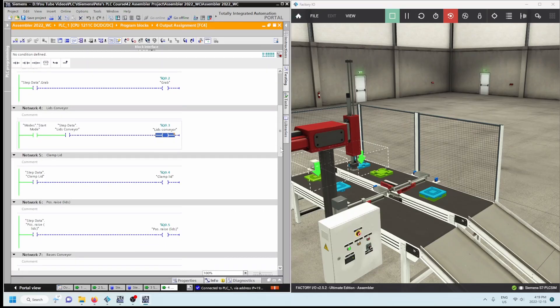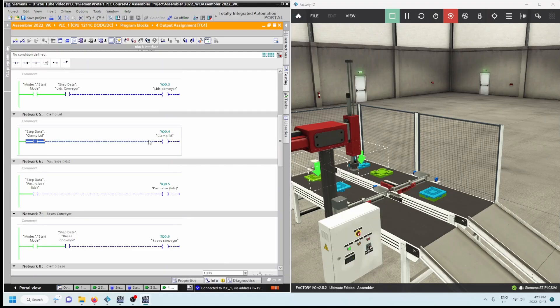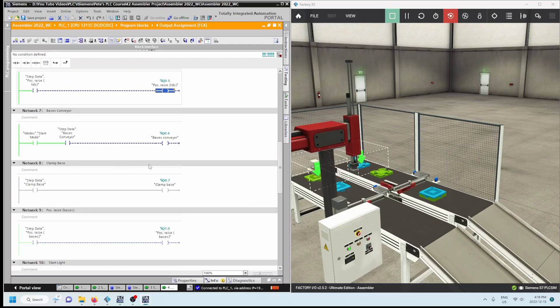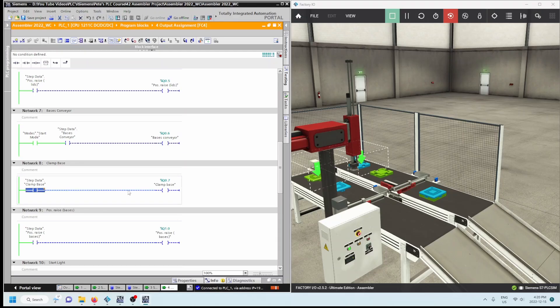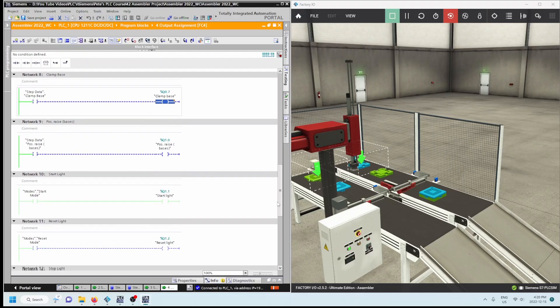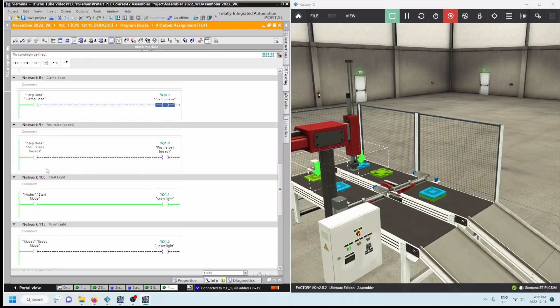For clamp lid: if step data 'clamp lid' is true then Q0.4 clamp lid is true. Network six, positive raised lids: if that was true in step data then Q0.5 turns on. For basis conveyor: start mode is true and base conveyors within step data is true, then turn on Q0.6. For clamp base: step data 'clamp base' is true, Q0.7 clamp base turns on. Each individual output has its own network, and that boolean value in the data block controls the output.